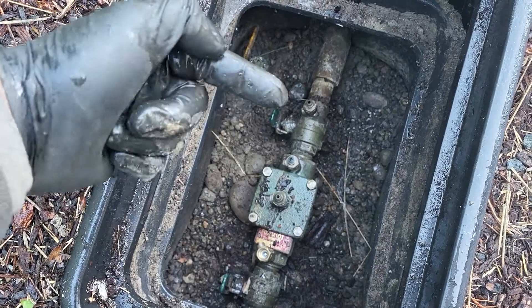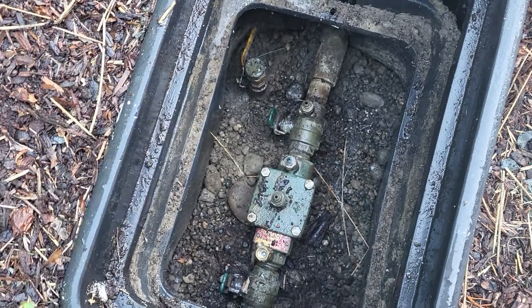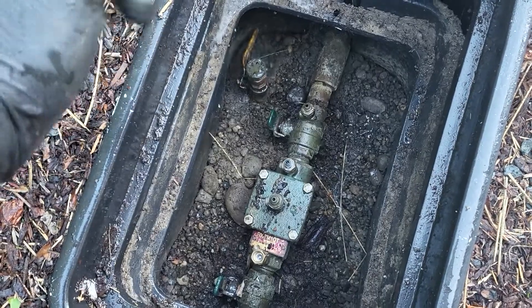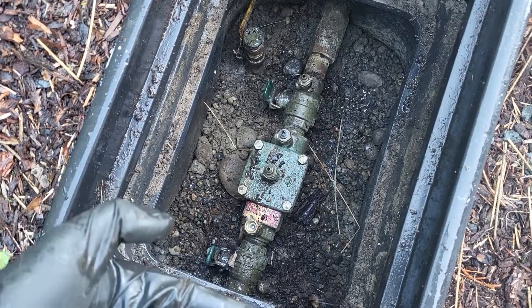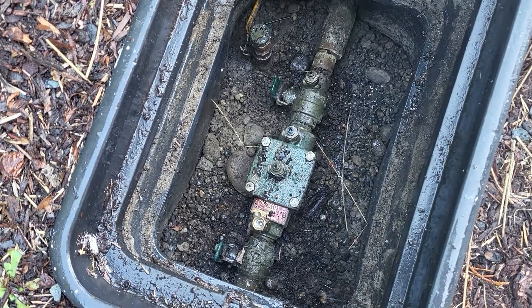Remember, number one test cock is always on the inlet side of the first isolation valve. I won't touch those because you can't have hose bibs or stop and waste before the backflow — at least where I'm at. It all needs to be past the backflow, so past your second isolation valve over here. But a lot of modern backflow preventers have flare fittings.